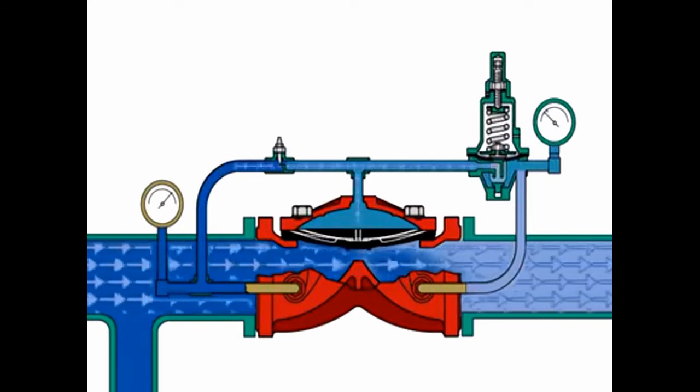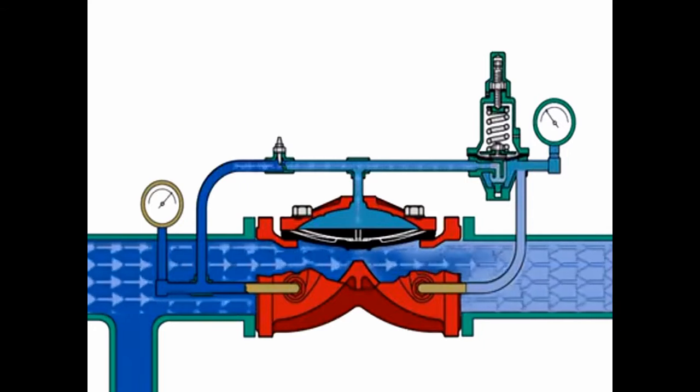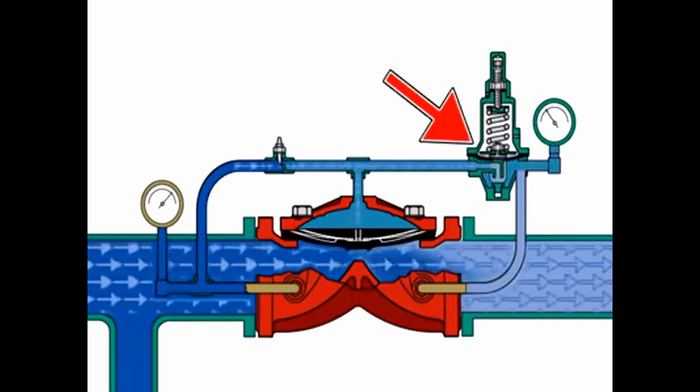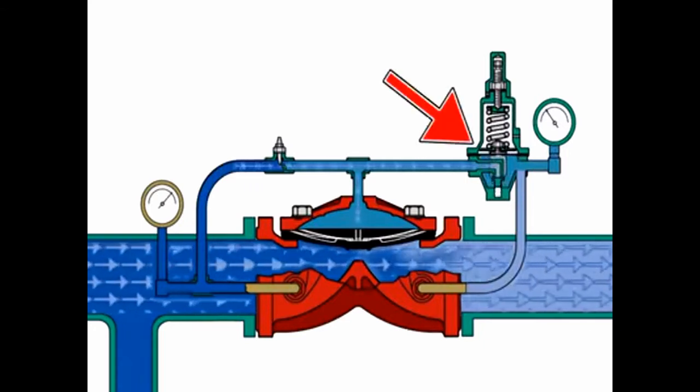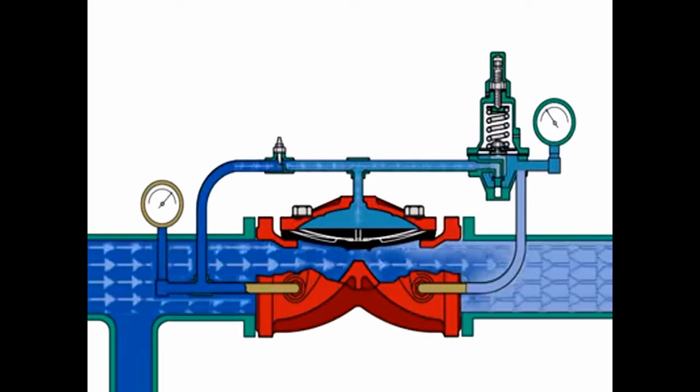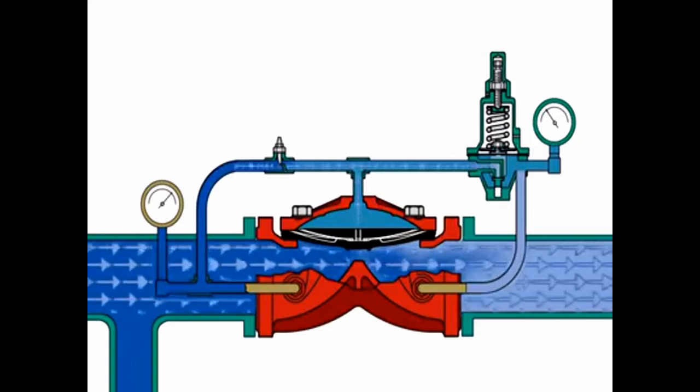As the flow demand continues downstream and the set pressure is met, the pilot valve seat closes to trap pressure in the diaphragm chamber. This keeps the diaphragm lifted at the same position and provides a constant set pressure.